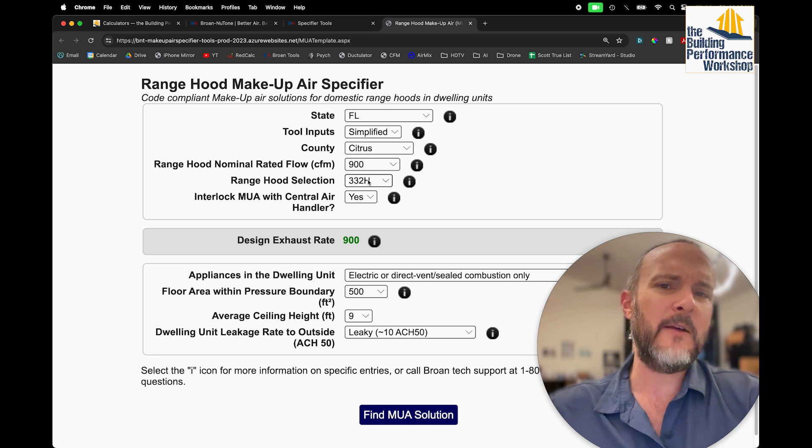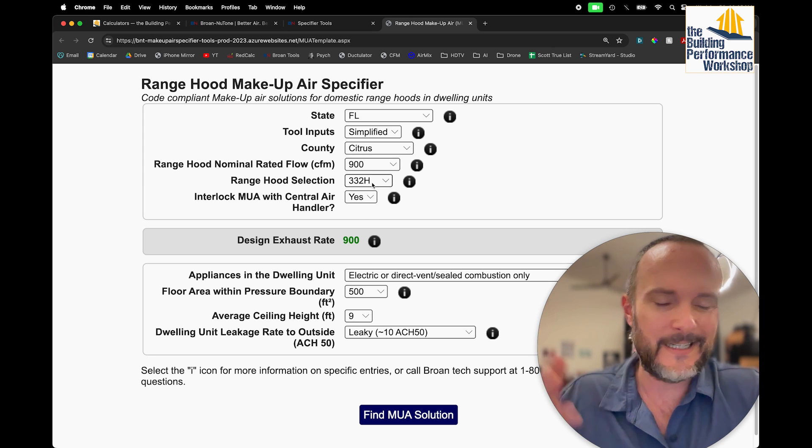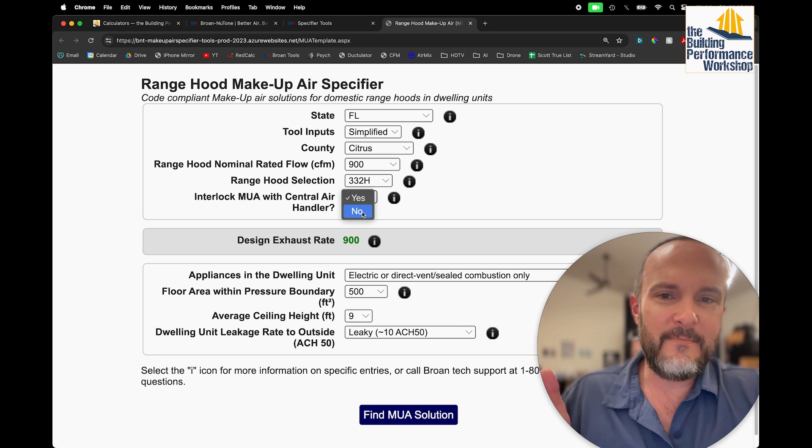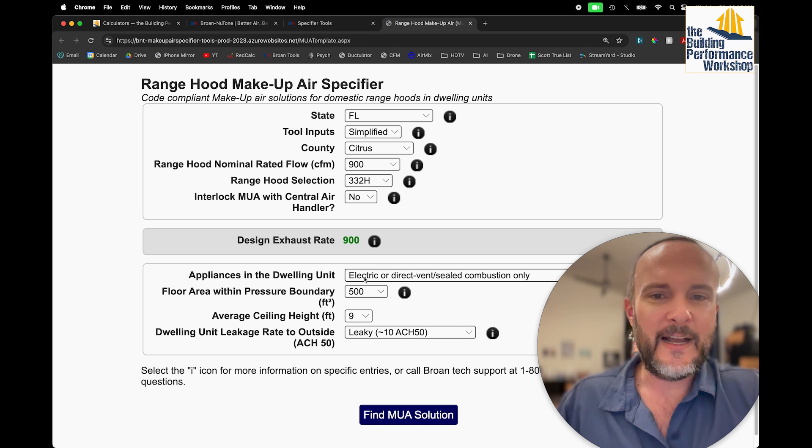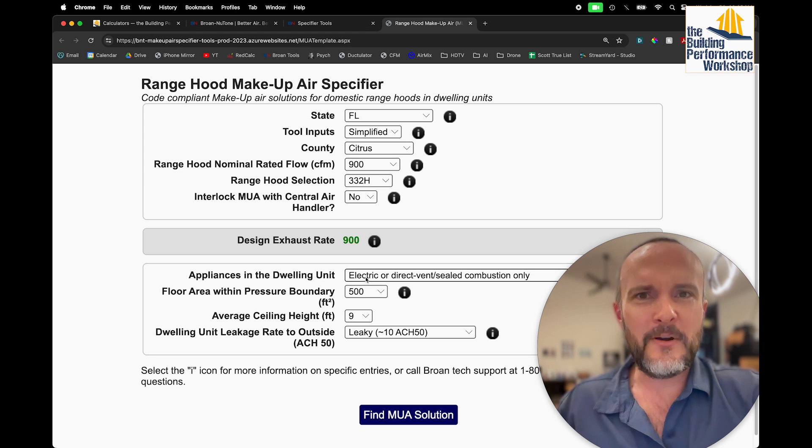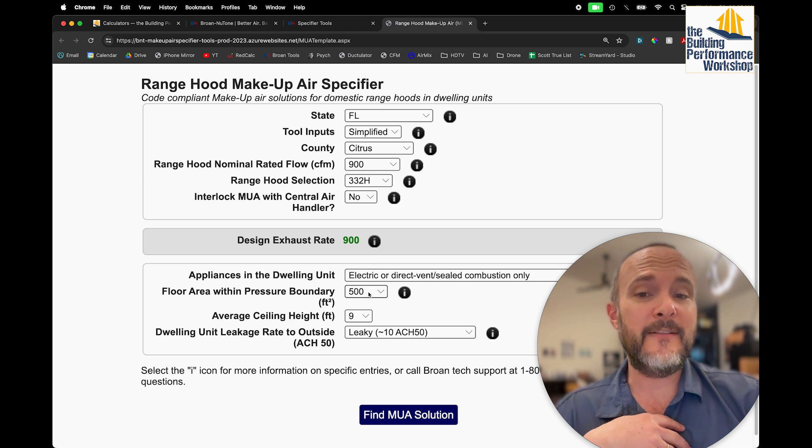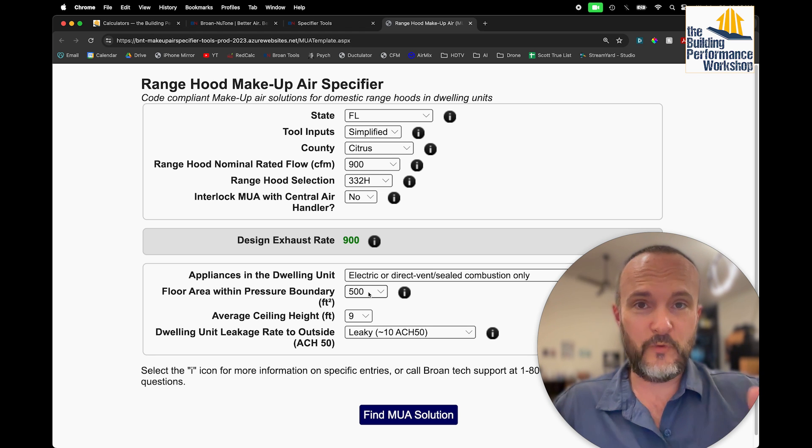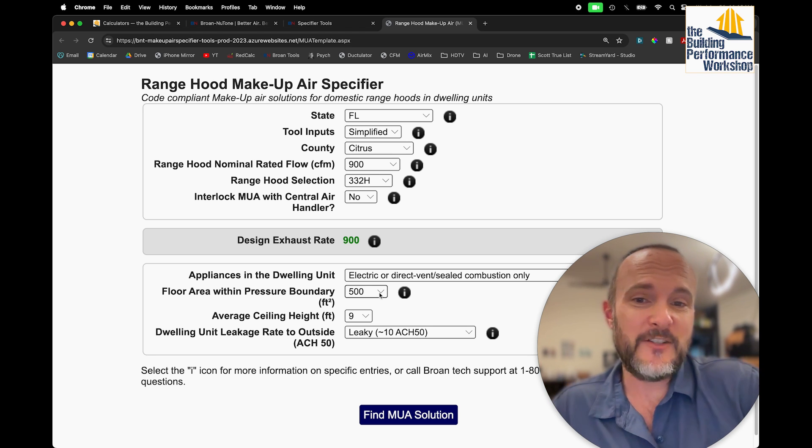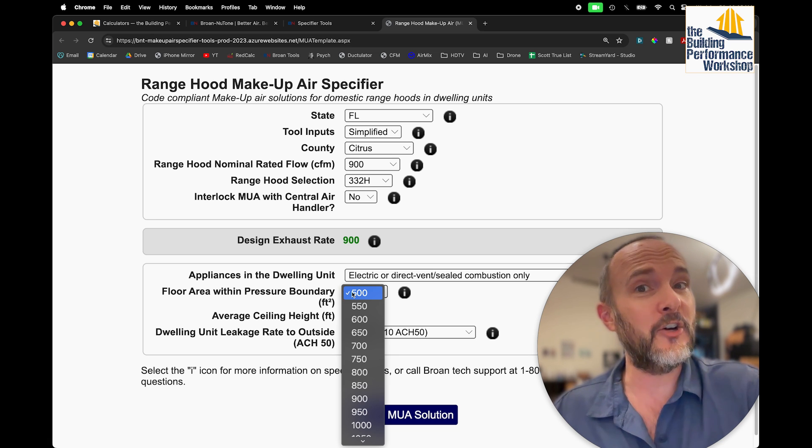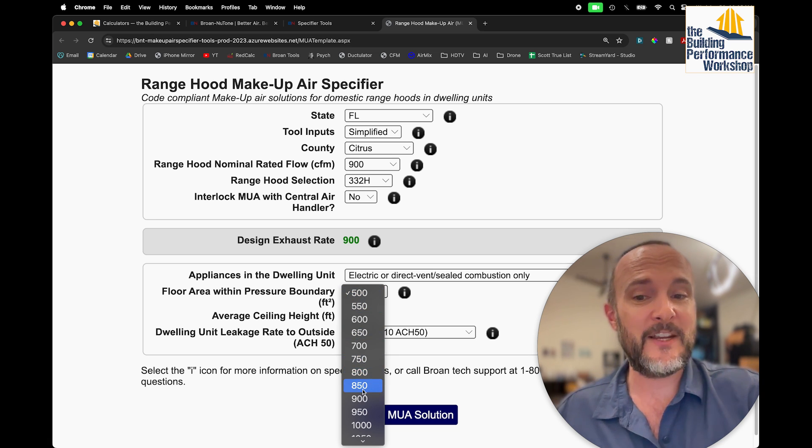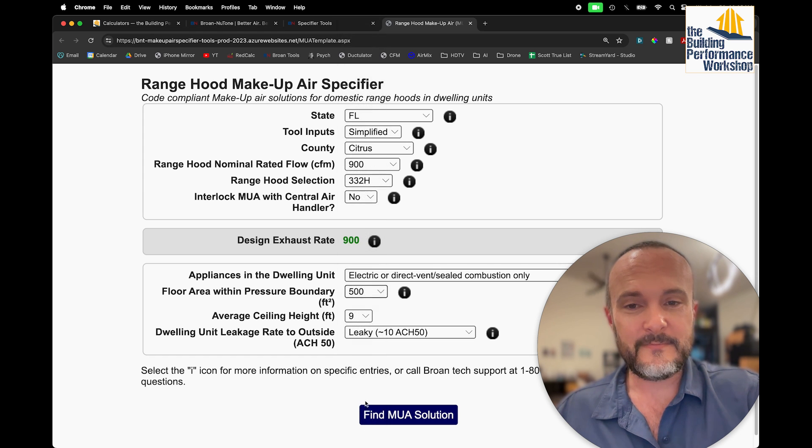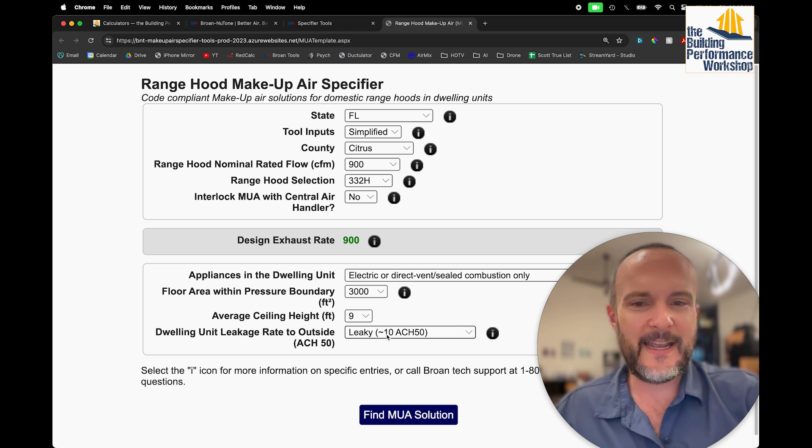I don't know how this is programmed to work. But let's just say that the range hood that this person is picking, and I just literally got off the phone with a client who had a 900 CFM Thermador range hood. So Broan is going to say, okay, well, you're using this, Broan. It doesn't matter. Or we're not going to interlock the Makeup Air with the central air handler. It's saying design air exhaust rate is 900. I'm not going to say anything else about it. It's saying, okay, do you have any combustion appliances that we should be worried about? I'm going to say no. I might, if I was uninformed, say that my kitchen is what I'm really worried about here. And I'd say my kitchen is less than 500 square feet. So I'll just leave it at that because there's not a smaller choice. This is the number for your whole house, by the way. So you pick your entire house, which let's just say is 3,000 square feet with 9-foot ceilings on average.